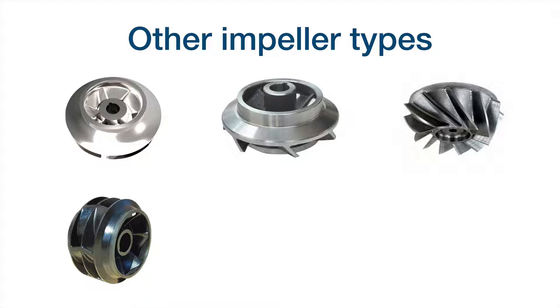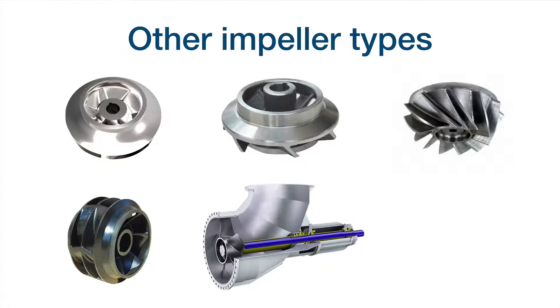Here is another impeller: a double-suction impeller, a back-to-back impeller — in fact two impellers joined at the back. This is used for applications requiring low values of NPSH, for example cooling water applications, pumping cooling water. This is an axial impeller — we can see the axial impeller inside this axial pump. And there are many others.